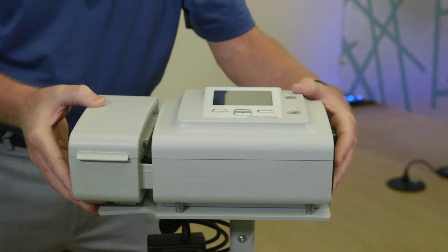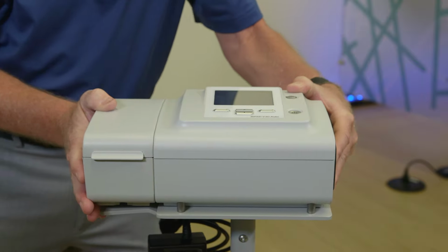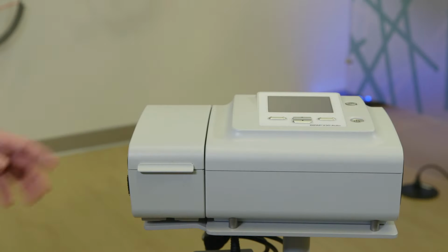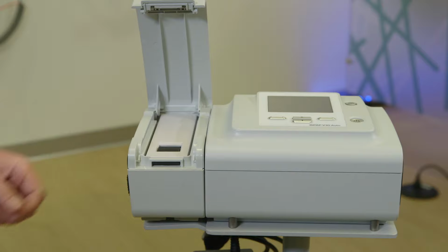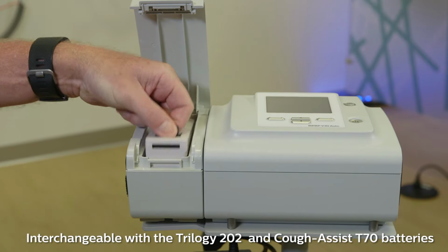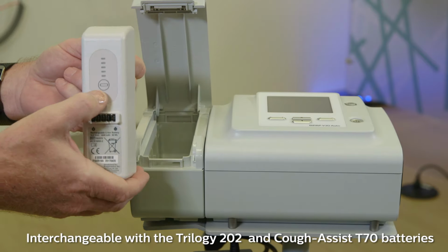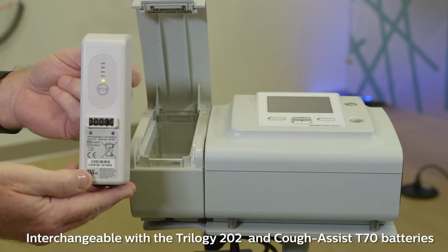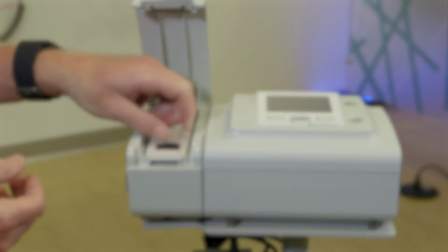To the left of the graphic user interface is the optional battery compartment. When opening the compartment, you'll notice that the battery is interchangeable with the Trilogy 202 and Cough Assist T70 batteries. However, when used with the V30, the life of the battery is up to 7 hours, depending on current settings.